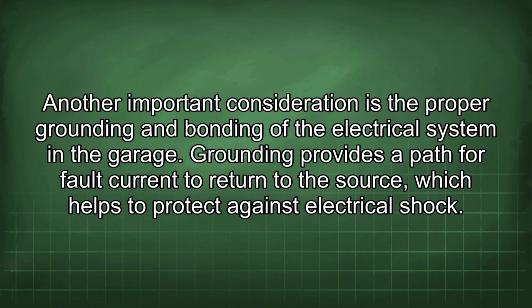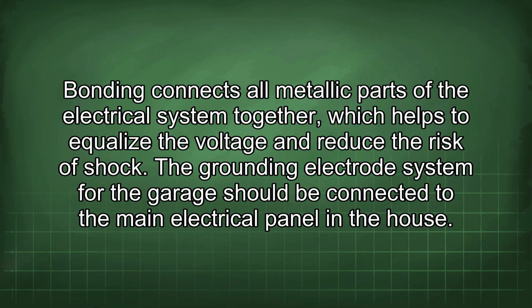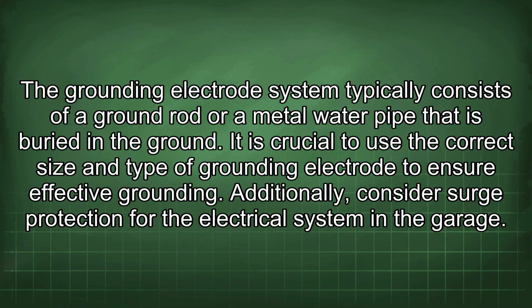Another important consideration is the proper grounding and bonding of the electrical system in the garage. Grounding provides a path for fault current to return to the source, which helps to protect against electrical shock. Bonding connects all metallic parts of the electrical system together, which helps to equalize the voltage and reduce the risk of shock. The grounding electrode system for the garage should be connected to the main electrical panel in the house. The grounding electrode system typically consists of a ground rod or a metal water pipe that is buried in the ground. It is crucial to use a correct size and type of grounding electrode to ensure effective grounding.